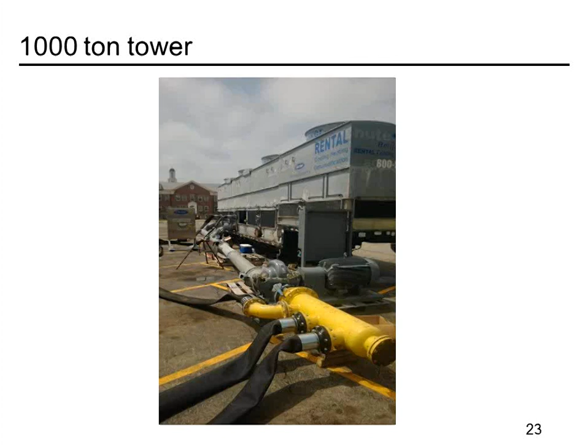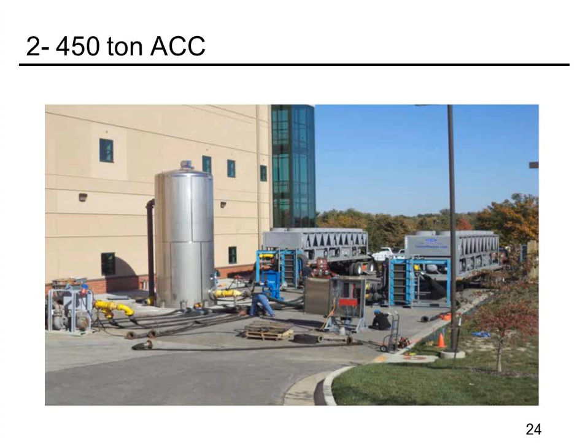Here's another plant. This plant had an ice building system, and they weren't able to keep up with peak loads. So they brought in a couple 450-ton chillers with heat exchangers to isolate it. So they have 900 tons. As the system was balanced, we were able to achieve running 31-degree water. They're getting 33-degree water out of the unit. So generally with heat exchangers, this isn't always possible. It is something we can analyze for you and see what it is going to be to fit your application. But in this case, we're running a glycol on one side of a heat exchanger, and we're able to get a 33-degree fluid out of the other side of it.